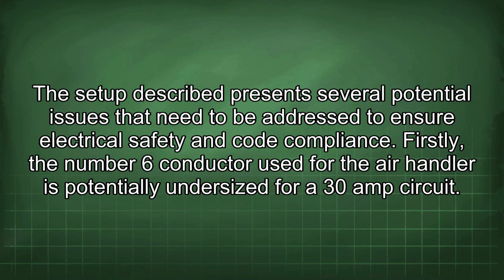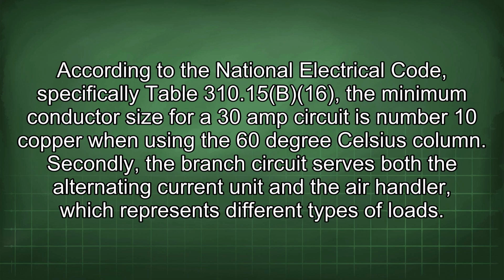The setup described presents several potential issues that need to be addressed to ensure electrical safety and code compliance. Firstly, the number 6 conductor used for the air handler is potentially undersized for a 30 amp circuit. According to the National Electrical Code, specifically Table 310.15(B)(16), the minimum conductor size for a 30 amp circuit is number 10 copper when using the 60°C column.